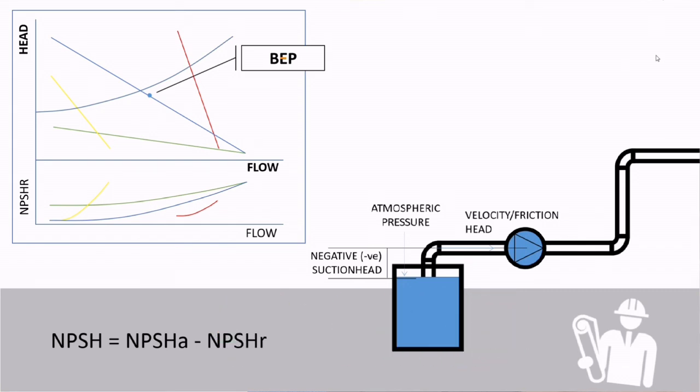NPSH is the net positive suction head available minus the net positive suction head required. NPSH-A is made up of the pump suction side static head, velocity and friction head at a given flow rate, and the atmospheric pressure. NPSH-R is what the manufacturer curve illustrates for your given flow rate. To avoid cavitation across the pump, the NPSH must be positive across all required flow conditions.